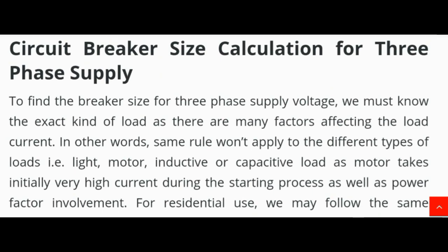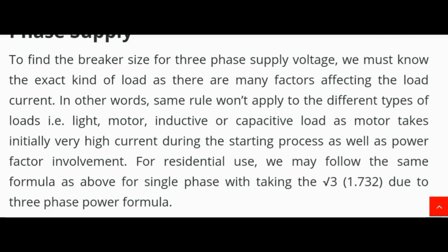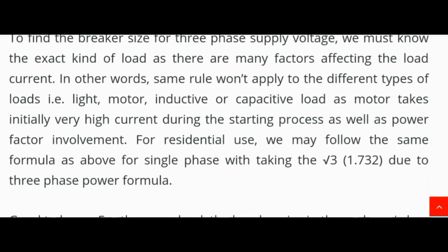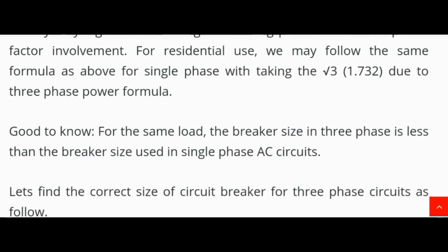The next topic is circuit breaker size calculation for three phase supply. To find the breaker size for three phase supply voltage, we must know the exact kind of load, as there are many factors affecting load current — for example, light, motor, inductive or capacitive load — as a motor takes initially very high current during starting and also has power factor involvement. For residential use, we may follow the same formula as for single phase, but taking the under-root 3 (which equals 1.732) due to three phase power formula.